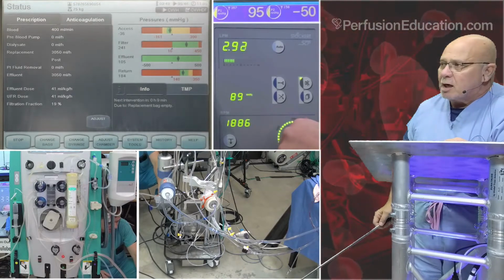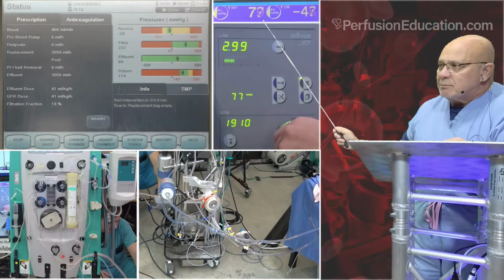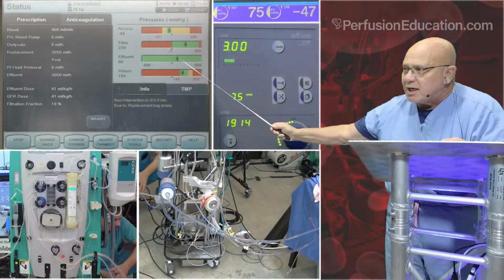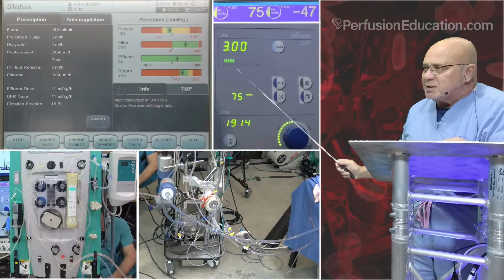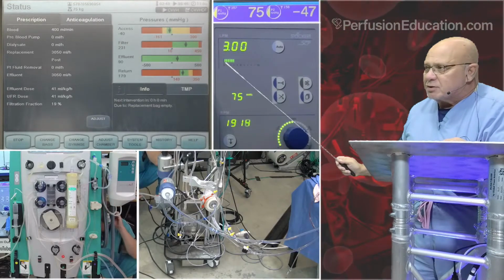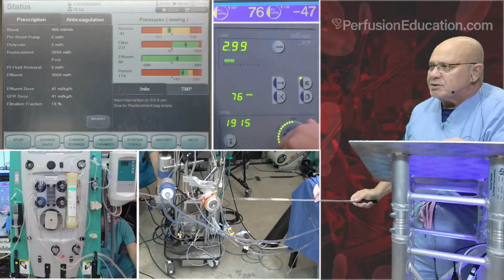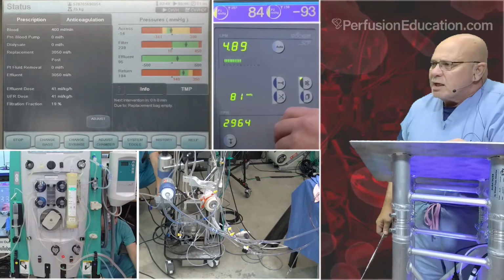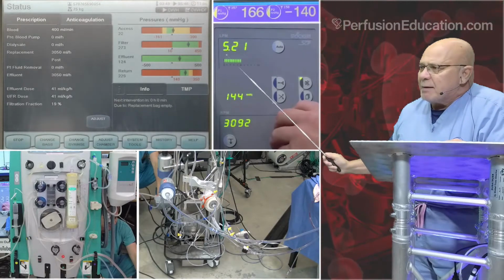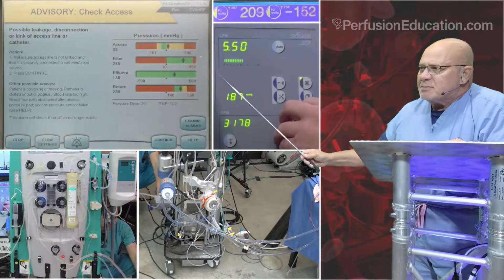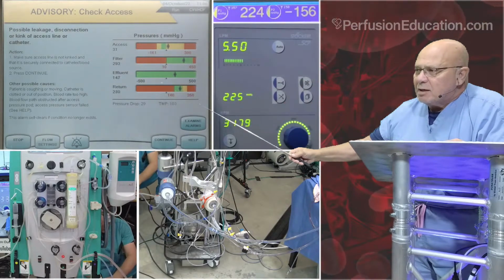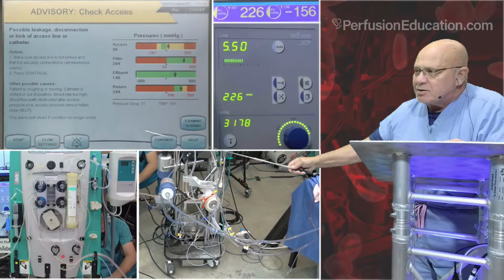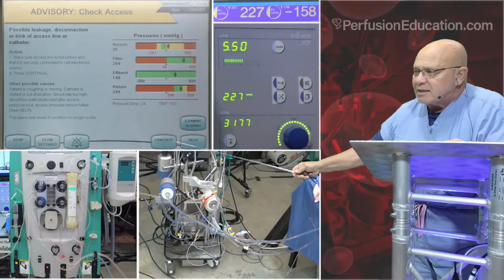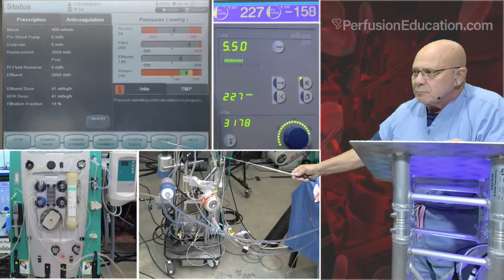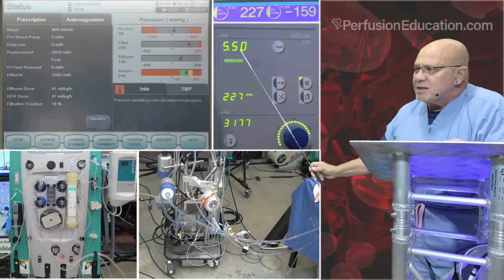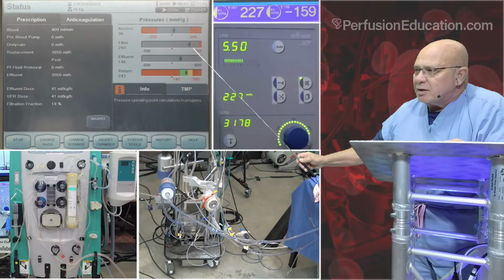Sometimes you will or won't get an alarm, but you see these numbers change. If these numbers change, these numbers are going to change. And of course you change this number and everything else is going to go along with it. So just ramp it up to 5.5 liters. And what you'll learn, you'll see everything kind of happen. And of course, remember I have resistance, but you're getting a check access alarm. It's not stopping, it's just telling you to check it. So go ahead and hit continue or override, whatever that says right there. There you go. And you can see it reset all of those pressures, but they're a little more unusual.